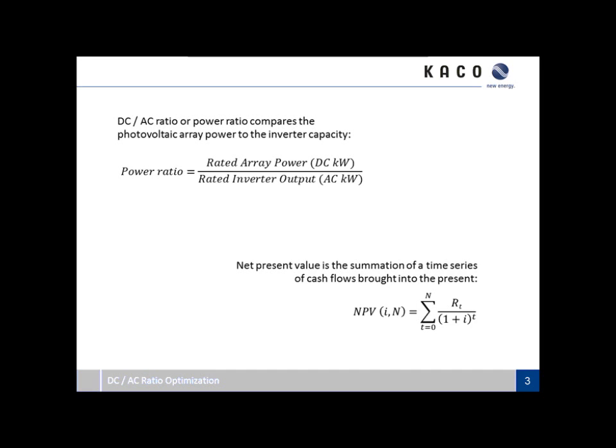DC to AC ratio, or the power ratio, is basically the maximum rated array power in DC kilowatts compared to the maximum rated inverter capacity. So it's the size of the rated DC array maximum compared to the rated inverter output. But we'll be looking at how net present value is affected by changing that DC to AC ratio. Net present value is, of course, the time series of cash flows — revenues and expenses — brought into the present via some discount rate, as shown in the equation here.